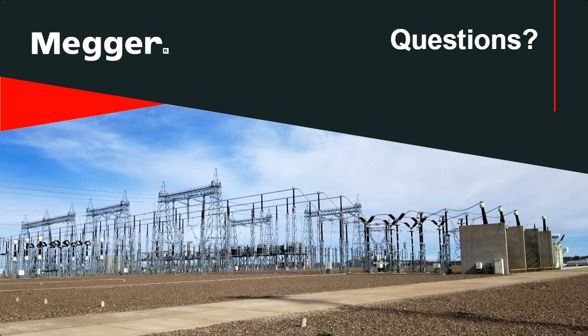So you're going to test this, and you're just going to get a power factor test, and it's going to be a relatively low power factor. Typically on SF6 breakers, mind you, it's going to be in the lower point 20s or sometimes point teens. So you're just looking at the insulation, or the power factor value of your contacts in SF6 gas. If you're looking at it with the oil, that's where you get more information, and that's where you have those 0.5 values because it is submersion oil. And then you do have the cross arms, and then they go up into the tulips whenever you're talking about OCB. So you get more valuable information with a power factor test that way.